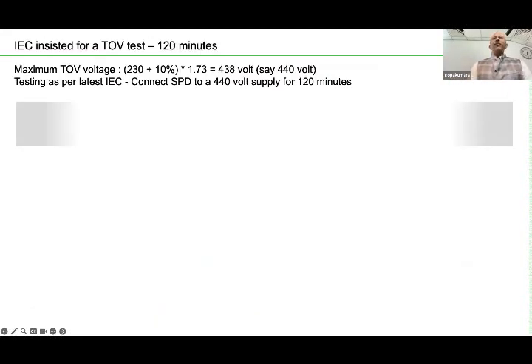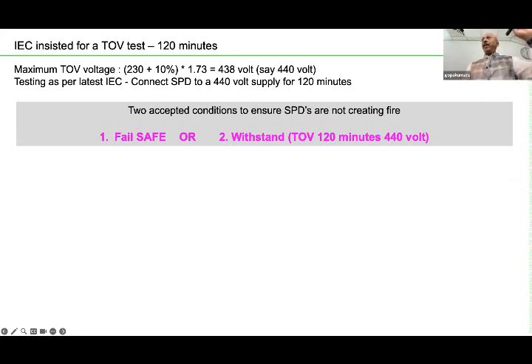So what is included in the standard is very important to understand. These kinds of situations are handled with a test parameter. Each SPD made in or complying to the latest standard has to be subjected to 400 volt for 2 hours. You connect the SPD for 2 hours at 440 volt. Now what can happen? One is the SPD can catch fire. Next, internally it has an internal thermal isolation. The next chance is this thermal isolator disconnecting. That means the SPD fails, but safely. So fail safe. The third case is it may withstand.